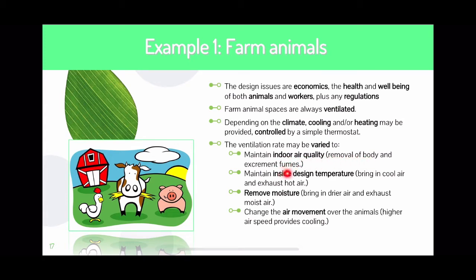Ventilation requirements include removal of body and excrement fumes — meaning the gases animals release, whether methane, decaying matter, or carbon dioxide. Also to maintain inside design temperature by bringing cool air in and exhausting hot air out, removing or introducing moisture via humidifier and dehumidifier, and changing air movement speed — higher speed provides more cooling during daytime, and slower air movement at night when animals are indoors.